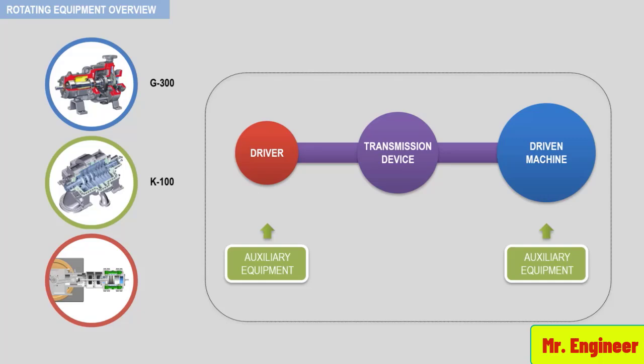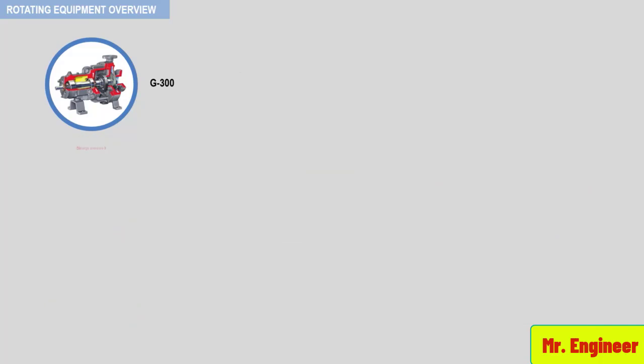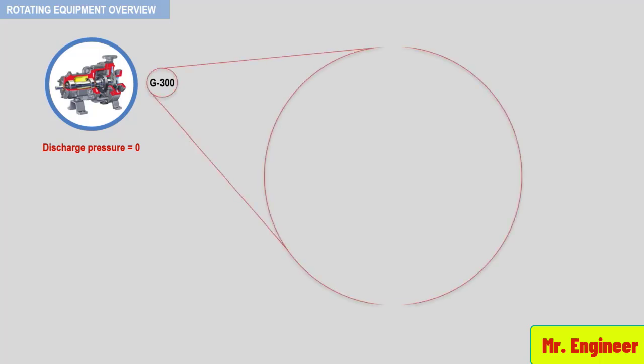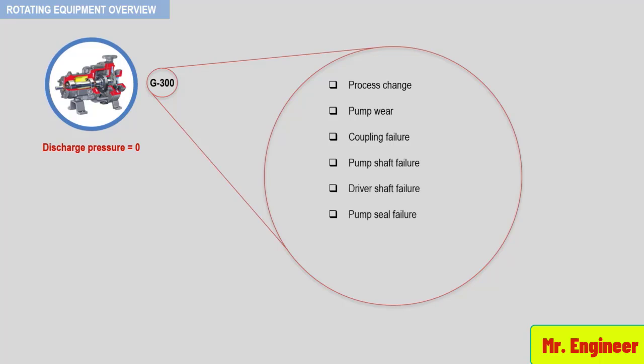Consider the following example. A call from the unit shift manager may state that the G300 discharge pressure is zero. So, what are the possible causes? A few are: process change, pump wear, coupling failure, pump shaft failure, driver shaft failure, pump seal failure, process valve closed, or steam inlet valve closed, if the driver is a steam turbine.